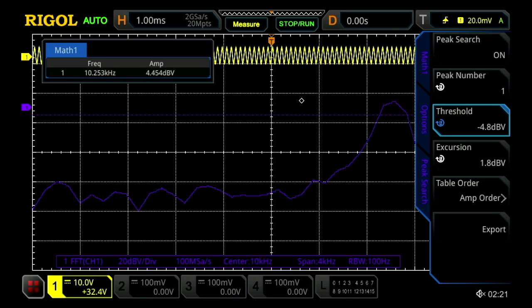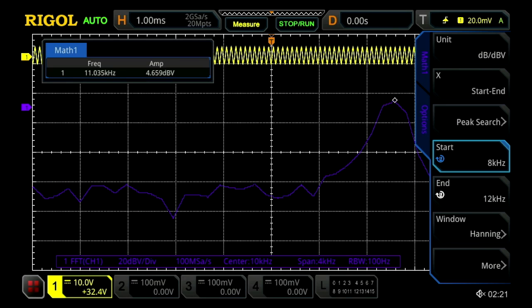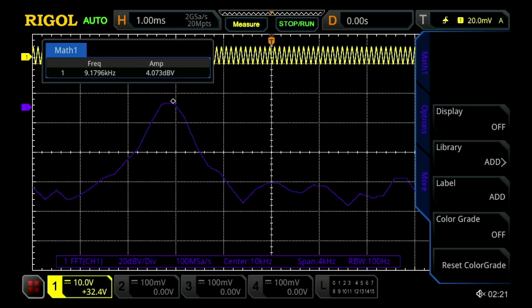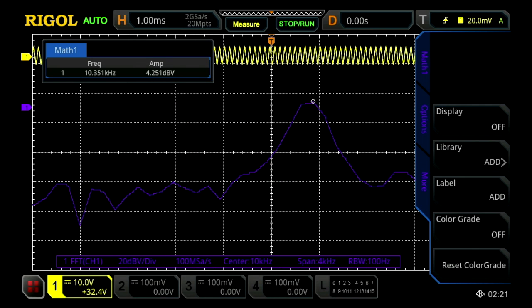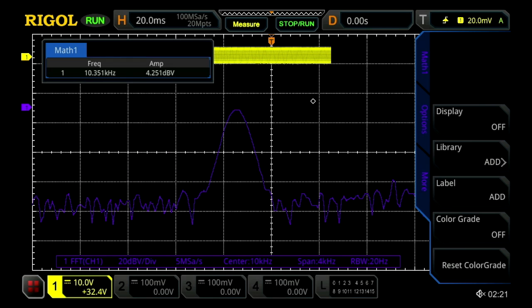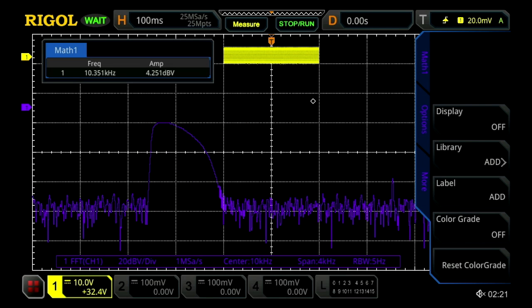The next thing we can do is back off a little bit, and then change our RBW settings. We'll also change this down to our 1 Hz RBW, just like before. And the way I'm doing this is with the horizontal scaling knob.